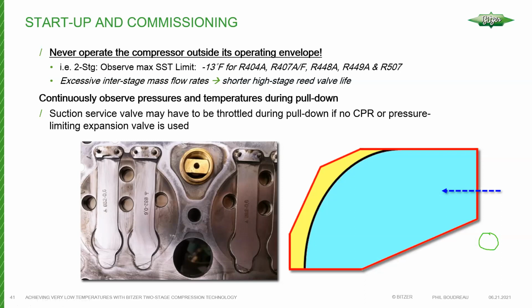When pulling down systems using two-stage compressors, note their maximum saturated suction temperature. In this case, for 404, 507, and some other refrigerants, minus 13 Fahrenheit saturated suction temperature is the highest that suction should operate at. If it's going to be higher because you need to pull that system down, it's very important, particularly if this is repetitive, so each run cycle requires this pull down, that you introduce, at the very least, maybe an electronic expansion valve with a programmed MOP, or maximum operating pressure, a CPR or crankcase pressure regulator, something like that. If it's a storage warehouse that happens to be operating at very low temp, in theory, you could just throttle the suction valves until you get the plant down to temperature. As long as you don't exceed the envelope, then you'll be okay.